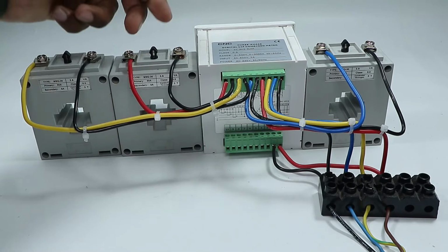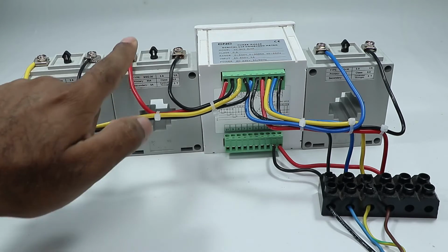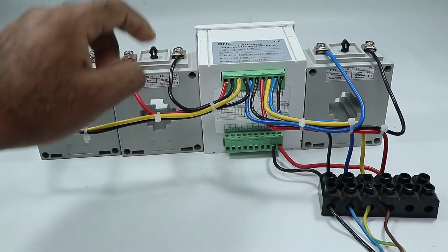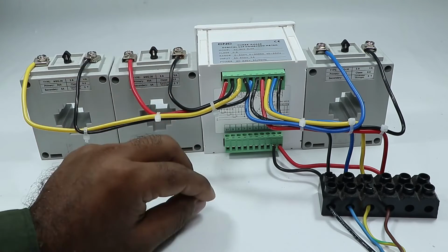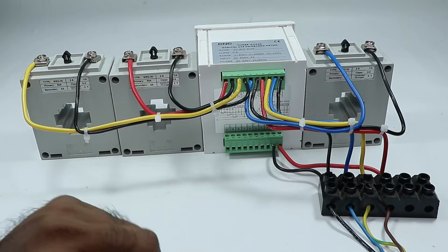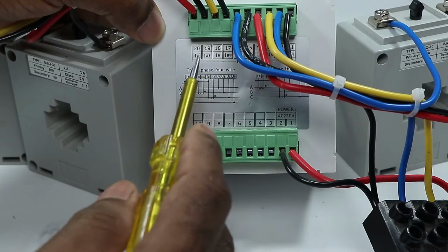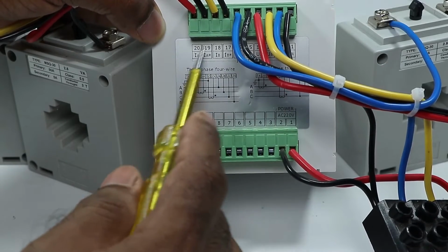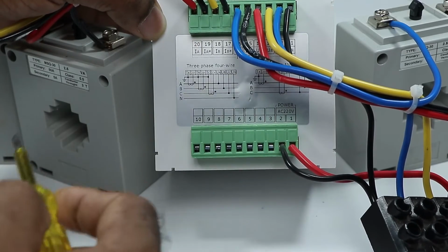Above this CT you can see two terminals given, one here and one here. With these two terminals, we have to connect a wire. After connecting the wire, at 19 and 20 number terminal on the meter, connect these two terminals with the wire.